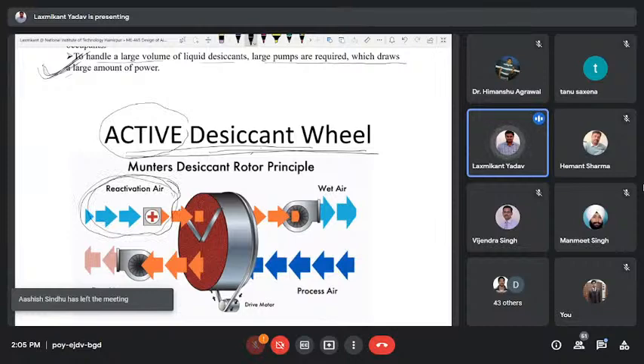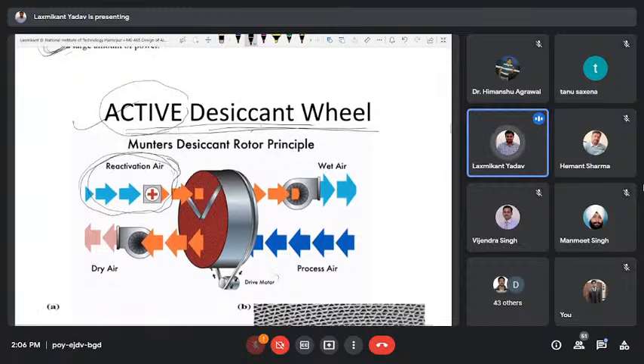In a further slide, we will also discuss the passive desiccant wheel. The passive wheel is the wheel that does not require hot air to operate. The active wheel requires hot air to operate continuously. So that's why it is called the active desiccant wheel. The passive desiccant wheel is the one which does not require hot air for the regeneration of the desiccant to operate continuously. Okay, so one motor is used to drive the desiccant wheel.